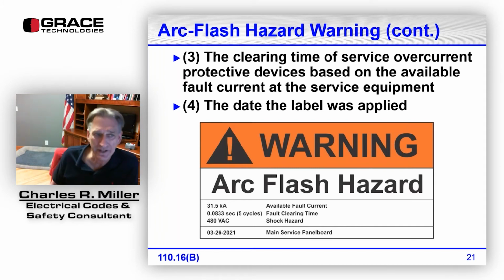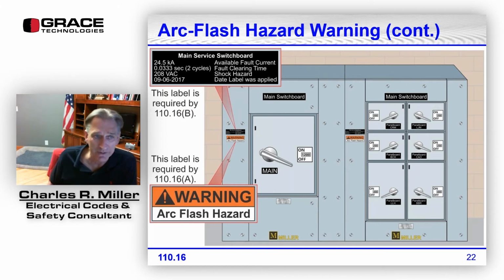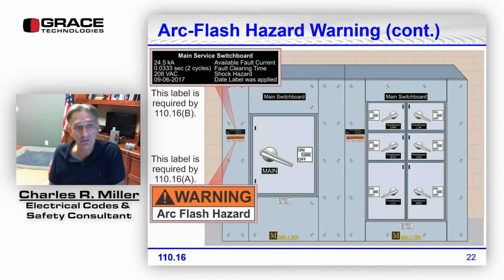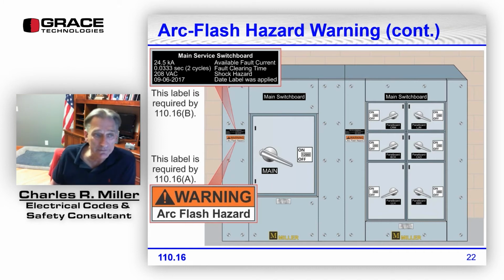All right, so here's another example. Arc flash warning. This is a plaque that's on the switchgear. It has a main service, so it's 24,500 amps, the available fault current, the clearing time is 2 cycles. The voltage on this is 208 volt, 9/6/17, September 6th is actually my birthday. Of course, I'm not gonna forget that. This label is required by 110.16(B).